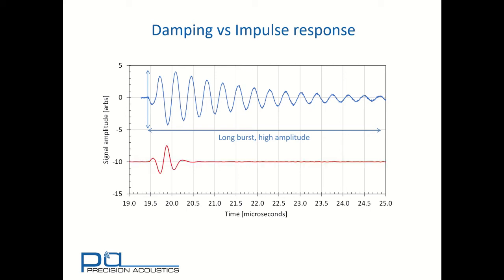In contrast, the highly damped transducer rings down very rapidly. It's a much shorter pulse but has much lower amplitude.